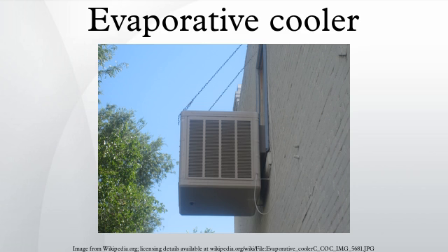Typical Aspen pads used in residential evaporative coolers offer around 85% efficiency, while Celdek type of evaporative media offer efficiencies of greater than 90% depending on air velocity. The Celdek media is more often used in large commercial and industrial installations.